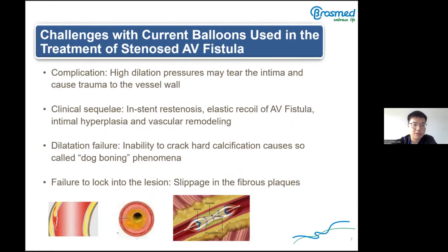Now let's look at the challenges with current balloons used in treatment of stenotic AVF. First, high dilatation pressure may tear the intima and cause trauma to the vessel wall, making patients feel more pain. Second, in-stent restenosis: elastic recoil of AVF, intimal hyperplasia, and vascular remodeling. Third, inability to crack hard calcification causes the so-called dog-boning phenomenon. Fourth, failure to lock into the lesion causes slippage in calcified plaque, like a watermelon seed.